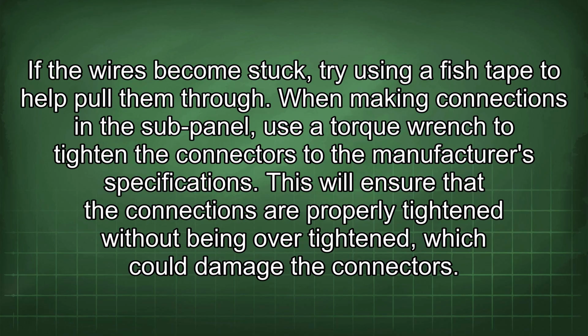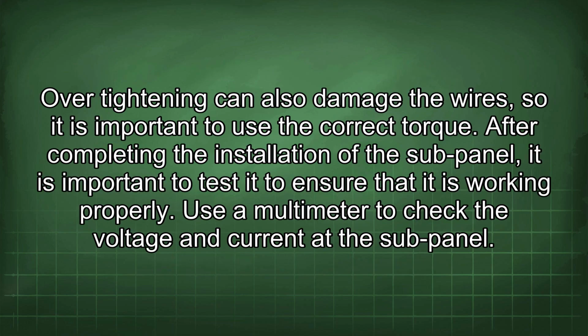When making connections in the sub-panel, use a torque wrench to tighten the connectors to the manufacturer's specifications. This will ensure that the connections are properly tightened without being over-tightened, which could damage the connectors. Over-tightening can also damage the wires, so it is important to use the correct torque.